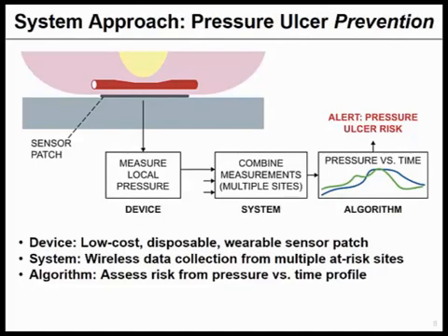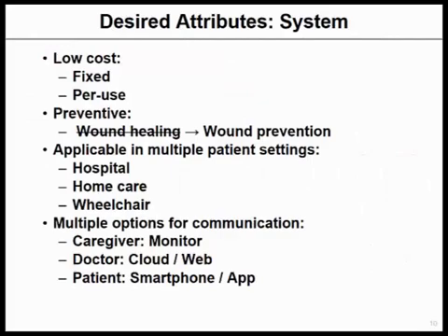So our approach is threefold. We're going to use a wearable sensor patch between the bony prominence and the bearing surface, measure the local pressure at the location at risk for the pressure ulcer, combine measurements from multiple sites in a system, and then monitor pressure versus time and alert the caregiver or the patient if there's a pressure ulcer risk, so you can move and relieve pressure on the location.